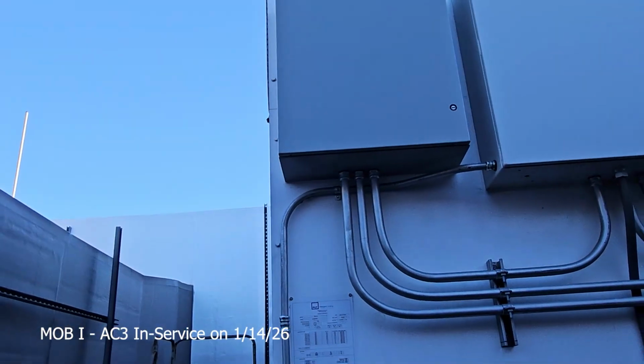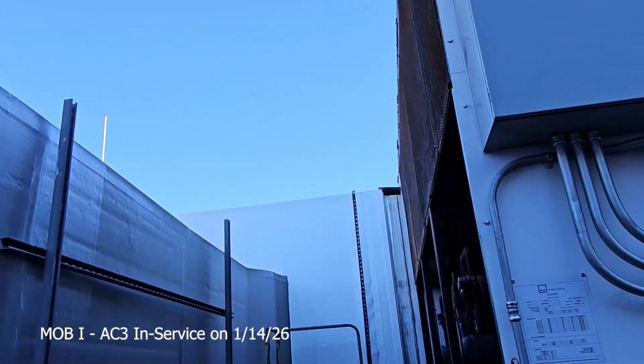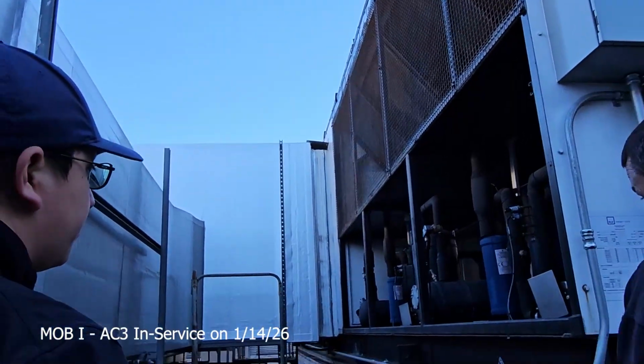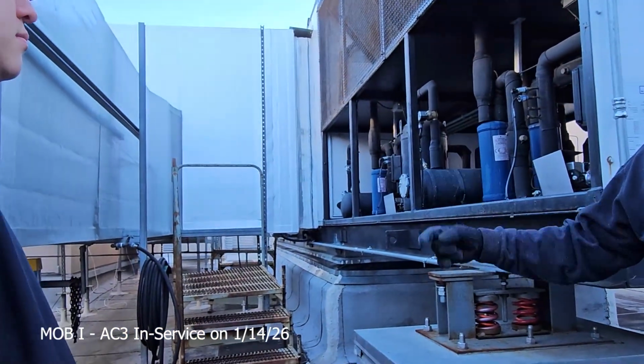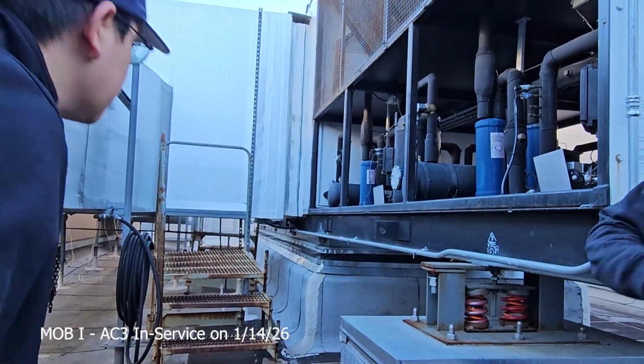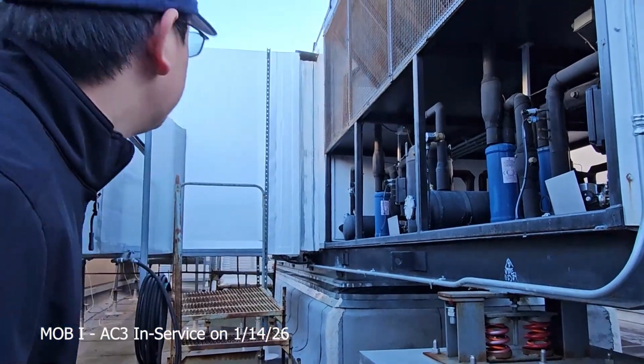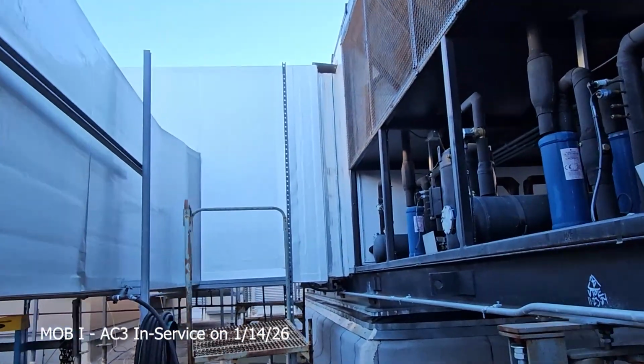You have your outside air humidity and temperature right there, and the static pickup is in the duct right there. So look under there. That's where your outside air humidity comes from. Same thing on the other unit, same exact spot.